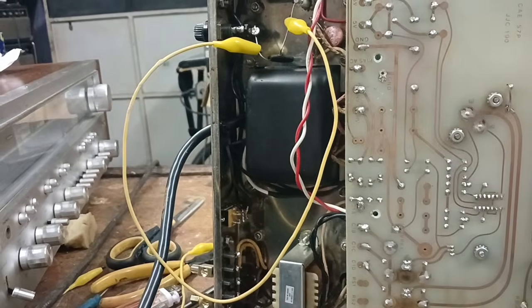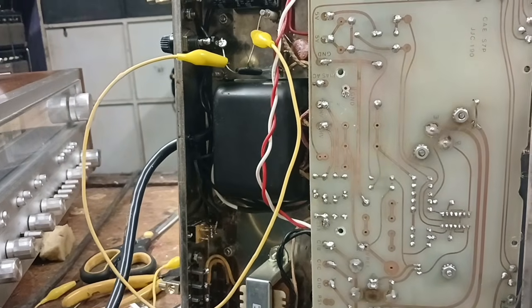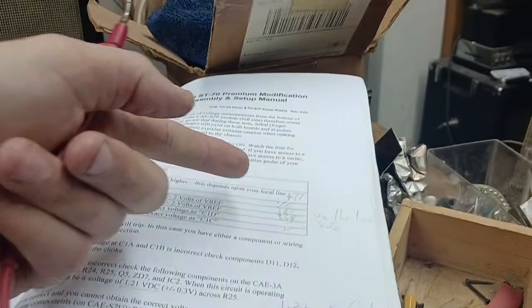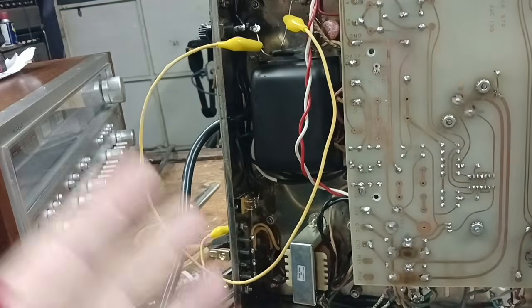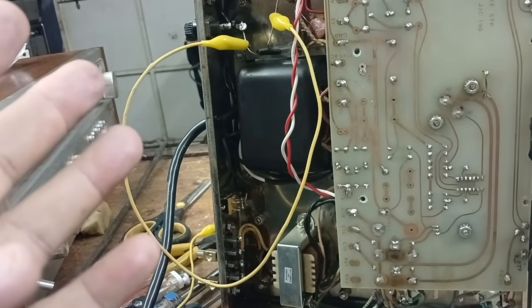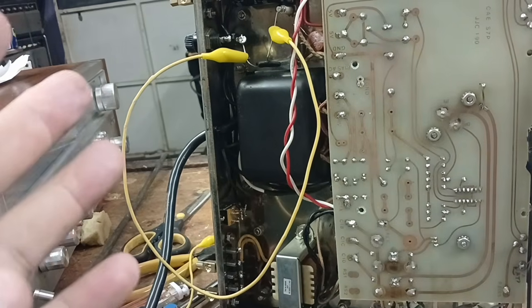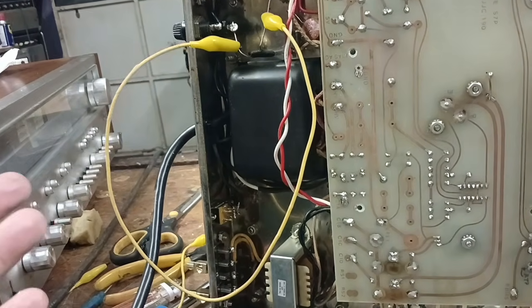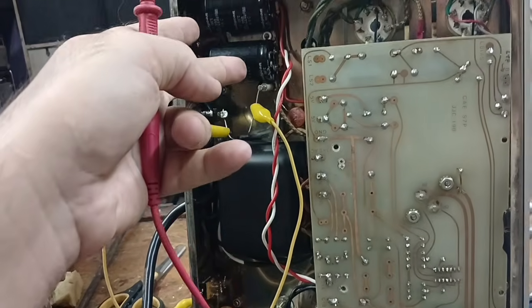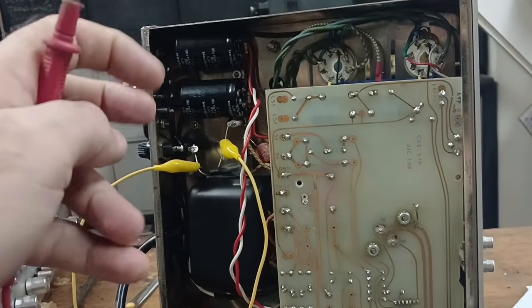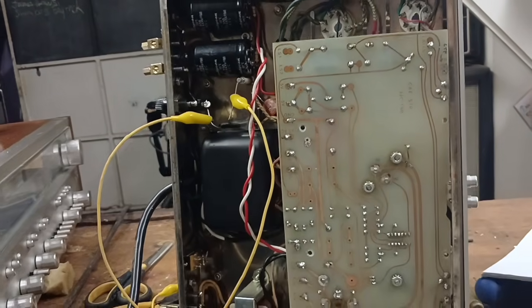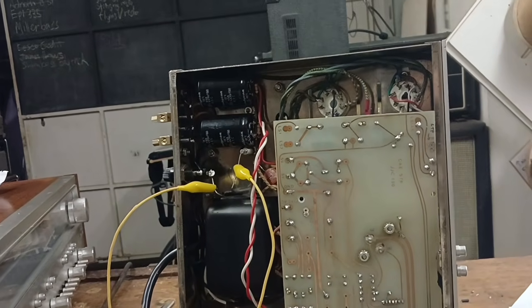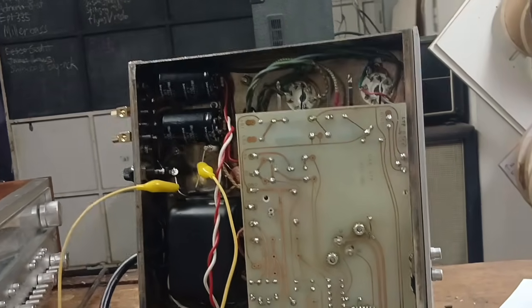Also to remember, I was saying that the voltage we tested never exceeded 500 volts. Therefore our capacitors were never in danger at their 500 volt rating. But now, who knows, it may cross 500. So I've left in place the safer version of the capacitor filter setup, which is rated at 800 volts.